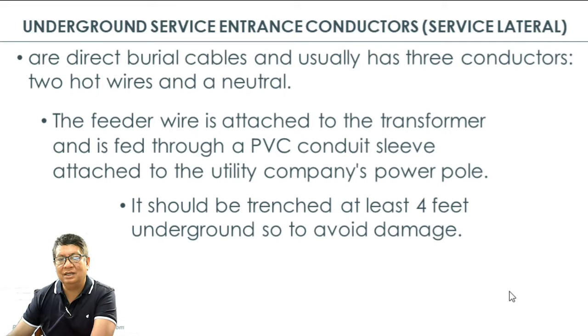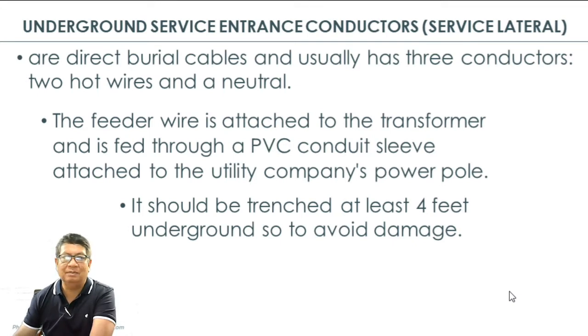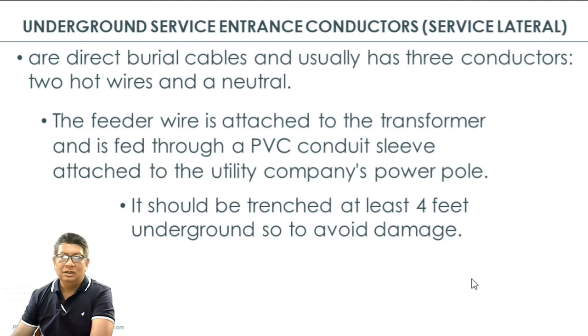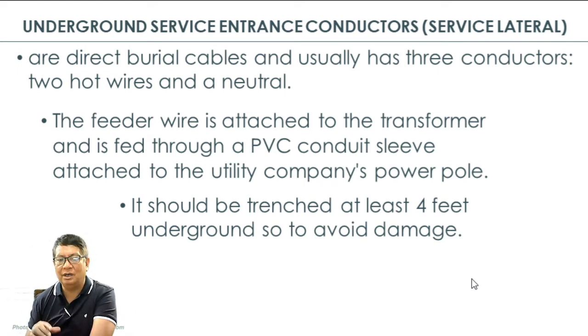The feeder wire is attached to the transformer and is fed from a PVC conduit sleeve — PVC meaning polyvinyl chloride. The conduit color here is orange. Orange is used for electrical conduits; blue or white is for water pipes. The conduit is attached to the utility company's power pole and should be trenched at least 4 feet underground to avoid damage. The underground PVC or rigid steel conduit should be buried about 4 feet deep so that heavy equipment passing over it will not break or damage the conduit.